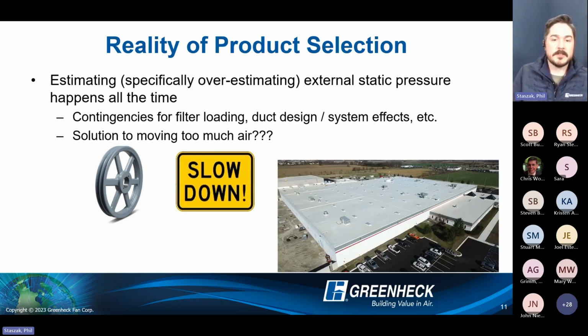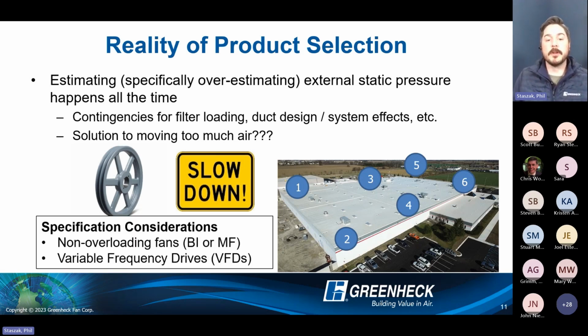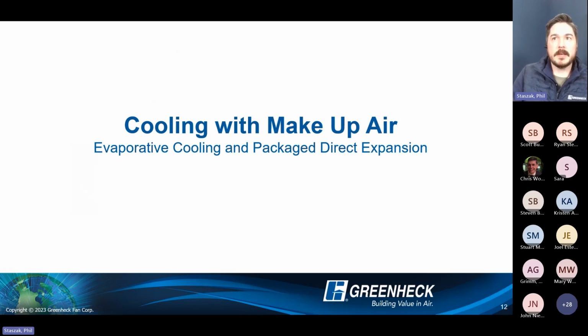So another benefit of mixed flow fans, direct drive fans, but also just considering putting VFDs on these very large systems that have fixed pulley arrangements, and considering putting the drives built in to just simply slow down that fan speed by changing the frequency output to the motor rather than having to change out belts and pulleys. All right, so that's the big, I guess, news as far as moving airflow. Just keep in mind, again, direct drive fans as a standard up to around 22,000 CFM. Forward curve fans are still very efficient in the higher airflow range, and we go all the way up to 65,000 CFM with one single makeup air unit, one big 50 horsepower motor driving 2 fan assemblies. The belt-driven fans do still exist in the higher airflows.